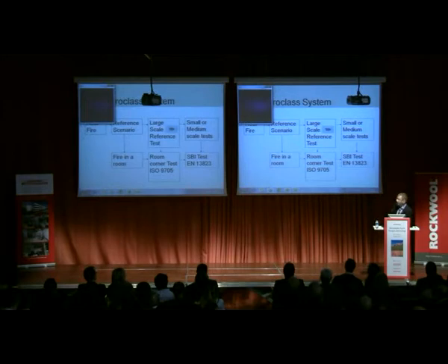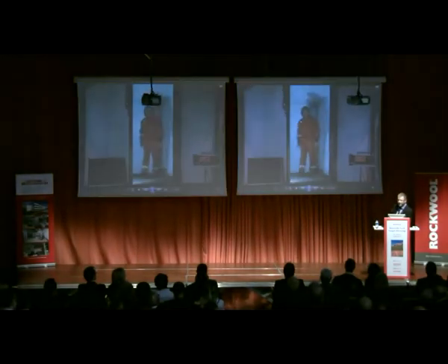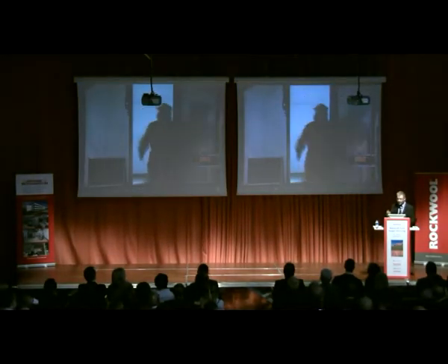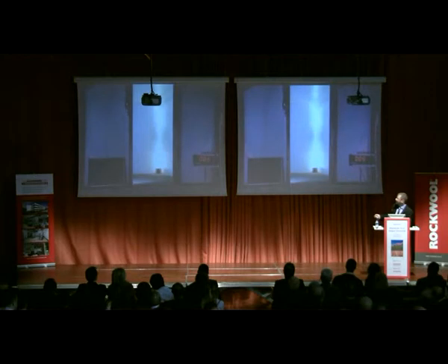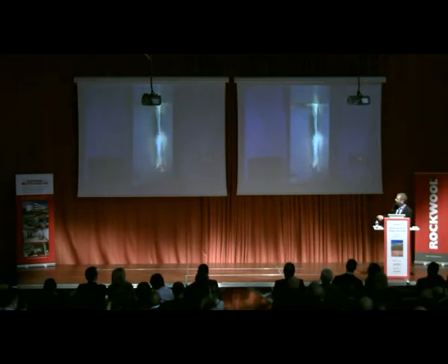I will now show you a room corner test made in an official fire testing laboratory. So first, what we will see here is a stone wool core sandwich panel. The principle is similar to SBI. We have a burner, gas burner, in a corner of a room, but we also have a closed room with a ceiling, and the output, the heating power of the burner is 100 kilowatts.